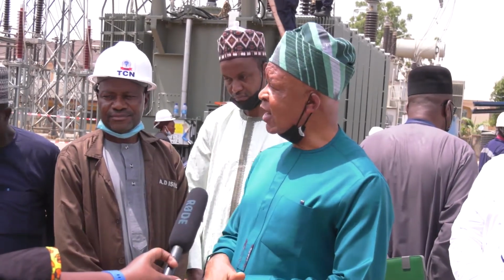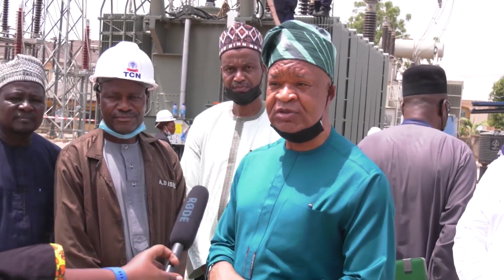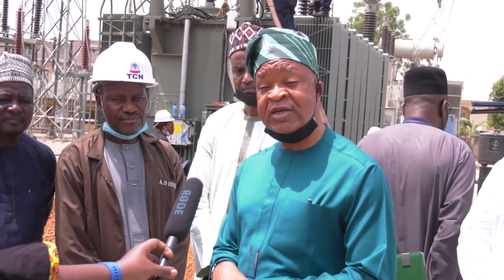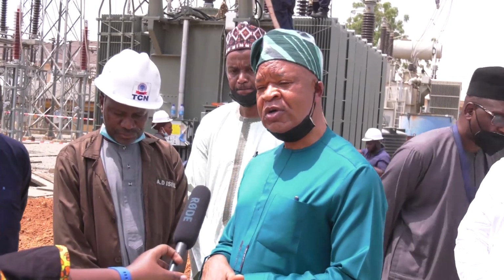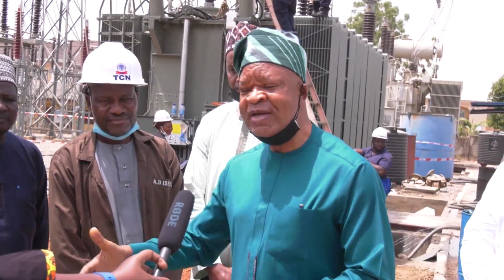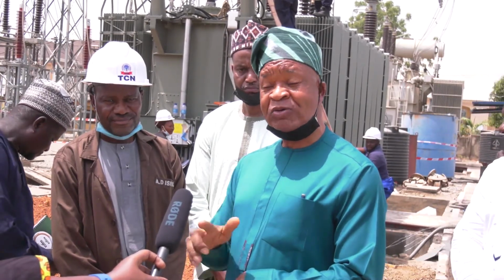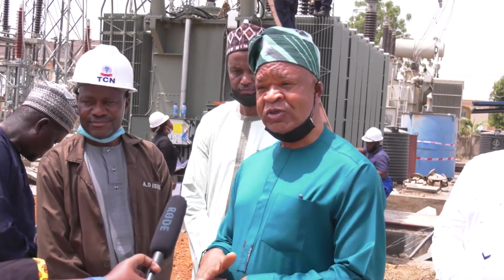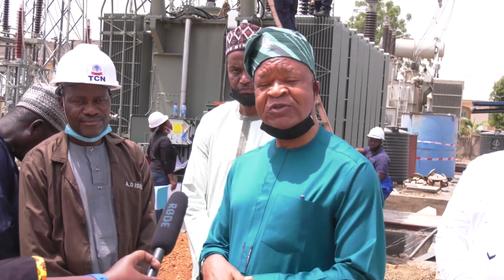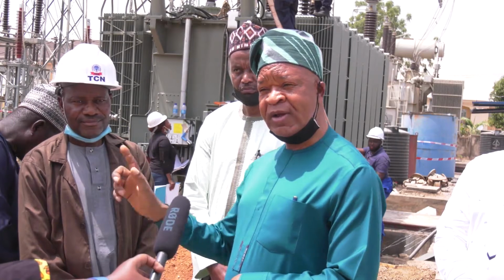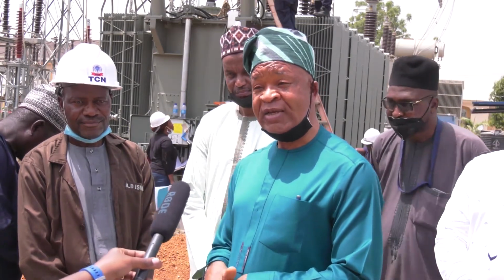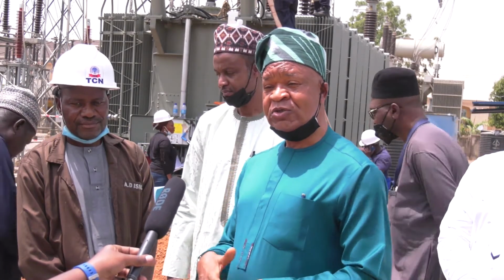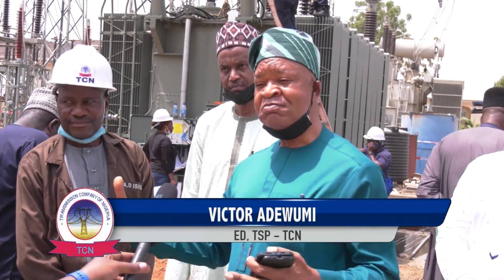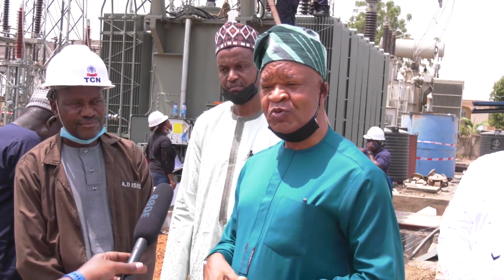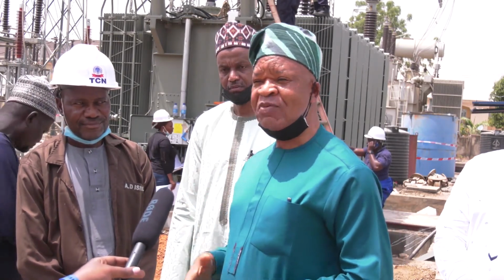We will add 2 additional 330 kV substations and 3 132 kV substations to the supply in Abuja. It's like doubling the capacity of Abuja. Not only that, that project will introduce a new line to the already 2 lines supplying Abuja. Presently, Abuja is being supplied from Shiroro and from Lokoja, but we are going to have a new line coming all the way from Lafia. So we are going to have 3 lines supplying Abuja, which means by that time Abuja will meet what we call N-2, meaning even if 2 lines are out, Abuja will still have supply.